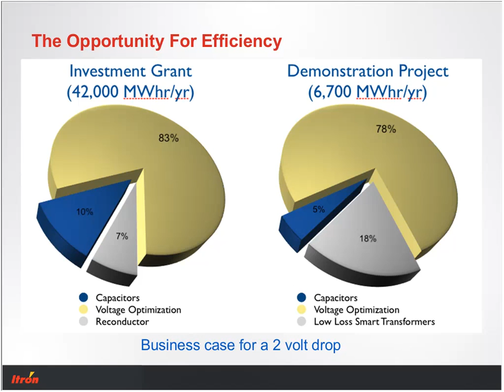We have assumed through some previous studies, part of which was the Distribution Efficiency Initiative in 2007 conducted in the Northwest, that we should be able to get a 2-volt drop. And what does that equate to? Well, that 2-volt drop for these two areas is a 5.6 megawatt power plant, in essence. That's how much load and losses will be reduced with that 2-volt drop.